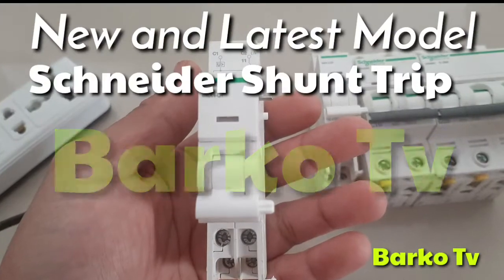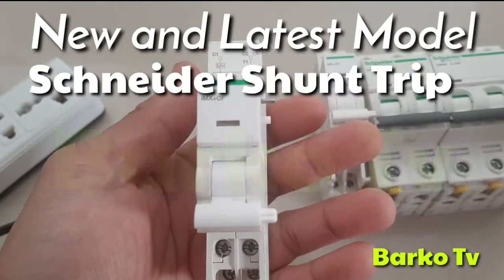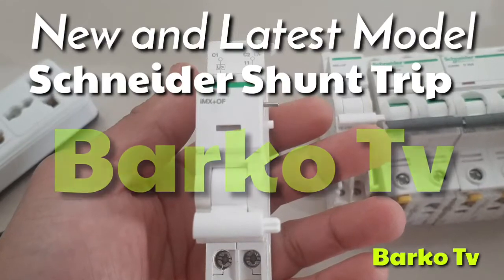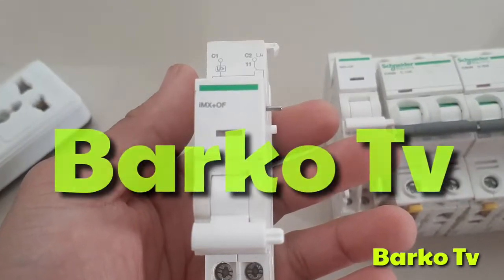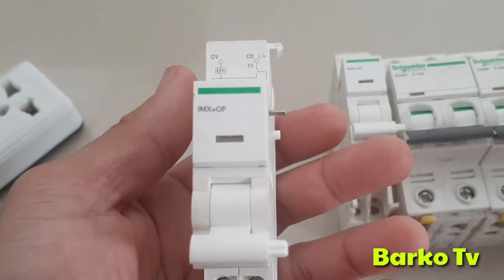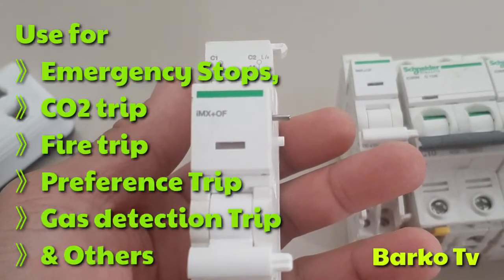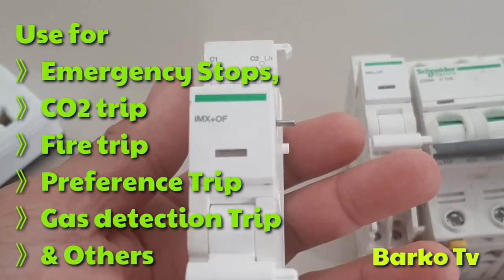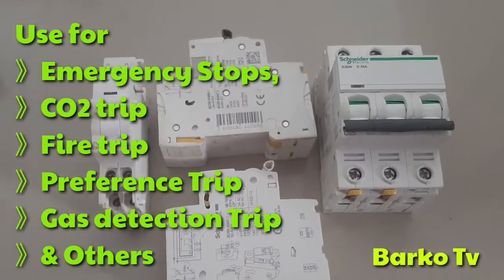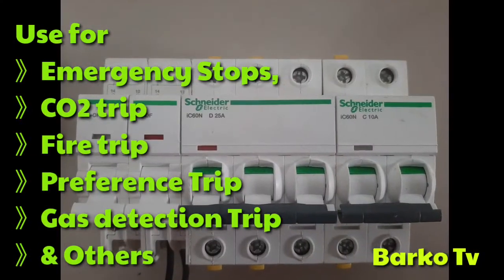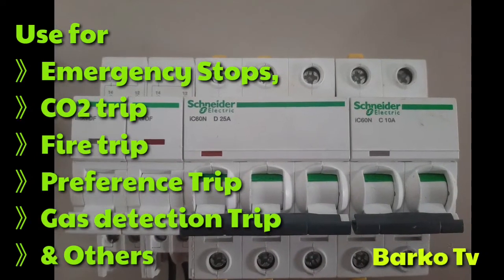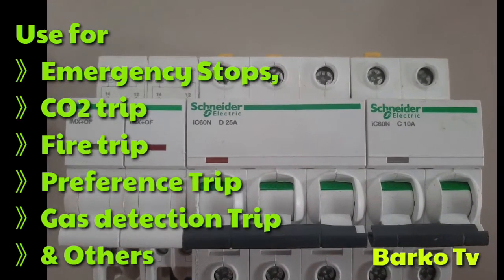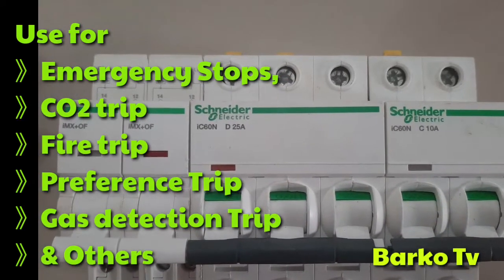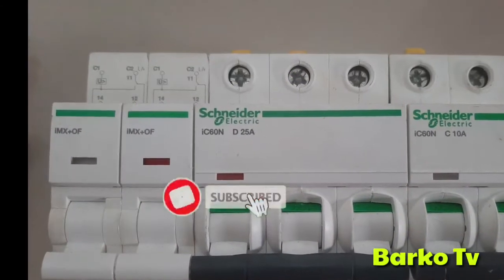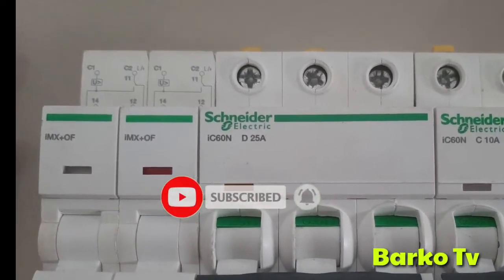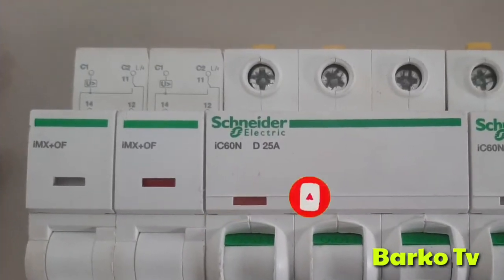Our topic for today is shunt trip. What is shunt trip? A device designed to switch the MCBs or power circuit breakers. It depends upon the attachment. But the shunt trip, when energized, a shunt release is instantaneously activated. The circuit breaker mechanism ensures a rapid disconnection. Means this shunt trip, when you supply the shunt trip mechanism or release, it will rapidly trip or rapidly disconnect the circuit breakers.